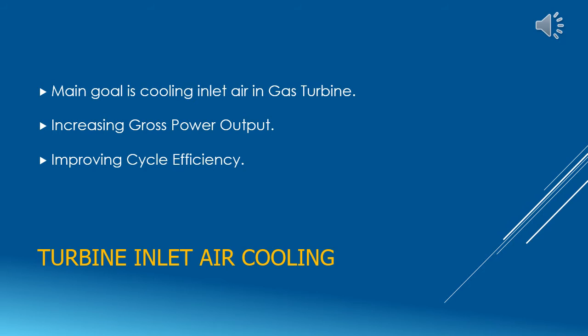Inlet air cooling is a method used to cool the air coming into the gas turbine, which is at ambient temperature. Methods of cooling stem from evaporative, absorption, and vapor compression, which is the method chosen for this study. The inlet air needs to be cooled to the required ISO conditions of 15 degrees Celsius, which in turn will benefit the cycle's efficiency and generate more power output.